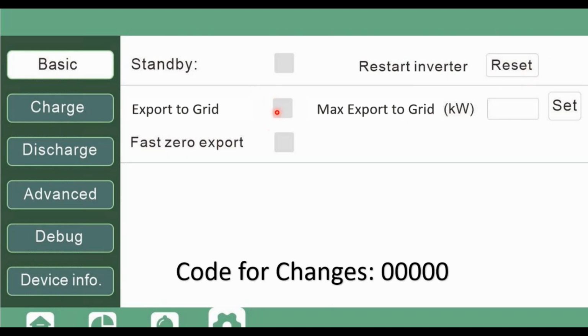Okay, when enabling the export grid, this is basically the feature that will allow you to export to the grid, and then you can control how much you want to export here. Okay, if you want to do fast zero export, you just select here and then disable export to grid. And to make these changes, it might ask you for a code, right? It's very simple. It's just 5 zeros to apply that code. Make sure that every change that you do, you click on set. Otherwise, it will not save the configurations.